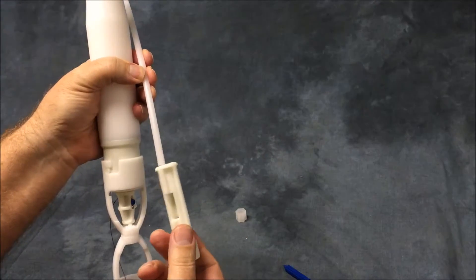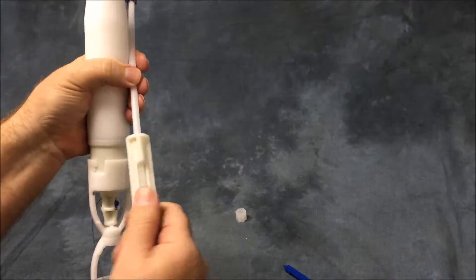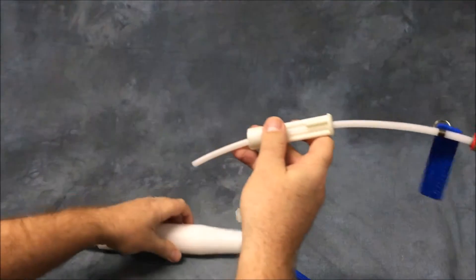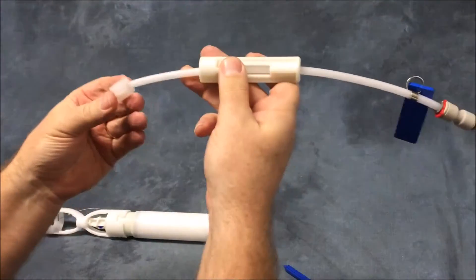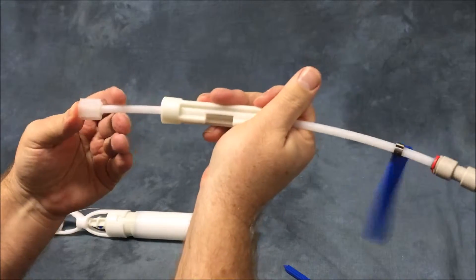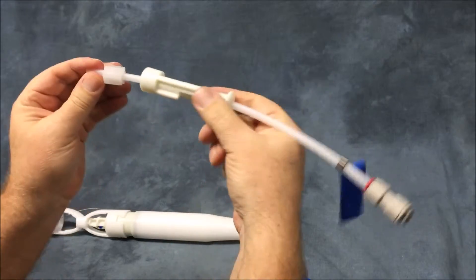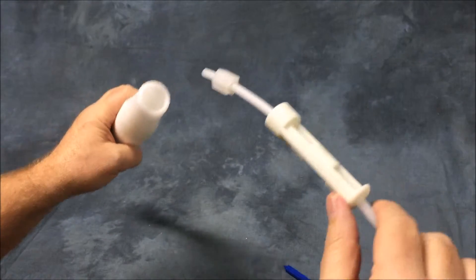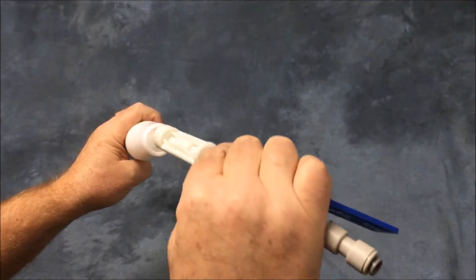You feed the polyethylene tubing through that line and then fit the ferrule, the nut, and ferrules through that line too. Then what you do is feed that into the top of the pneumatic actuator part.